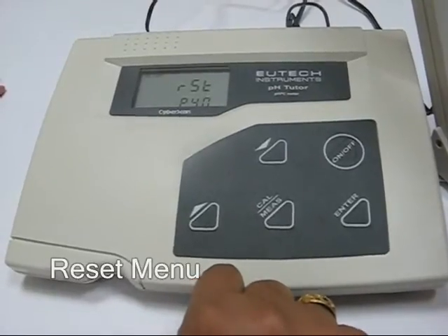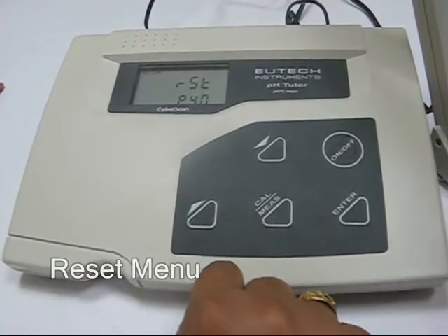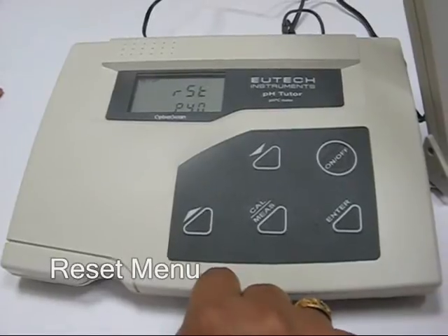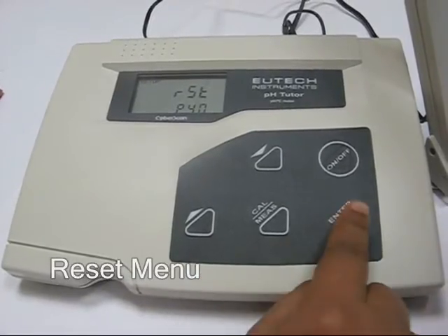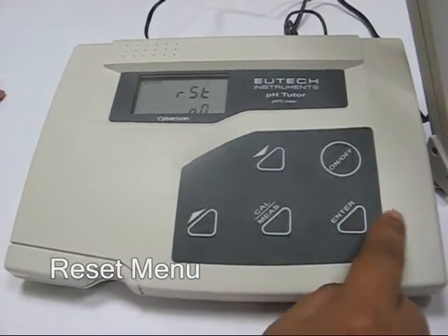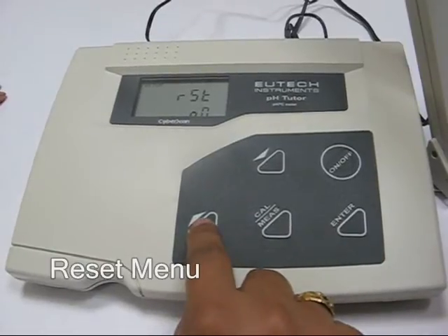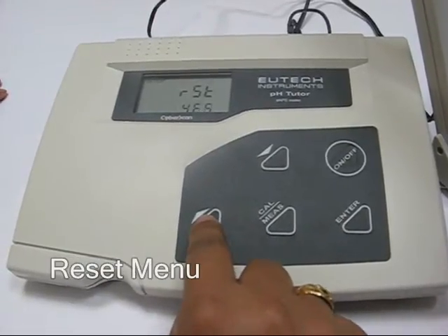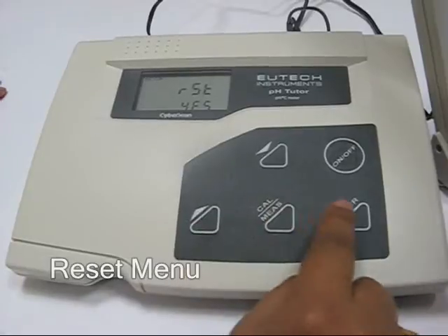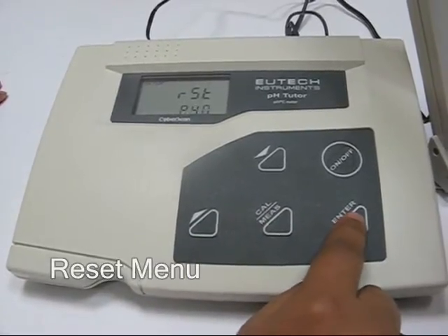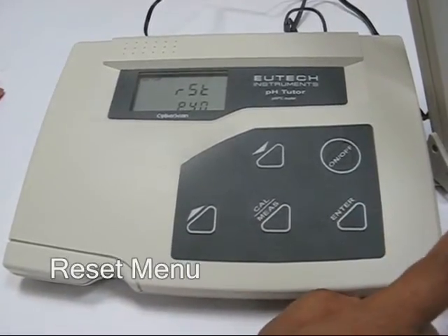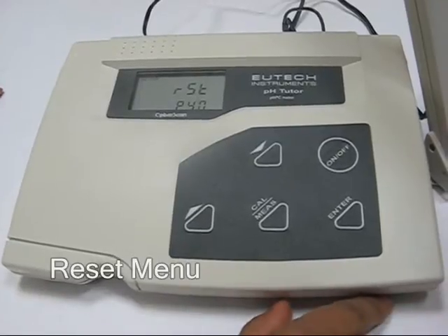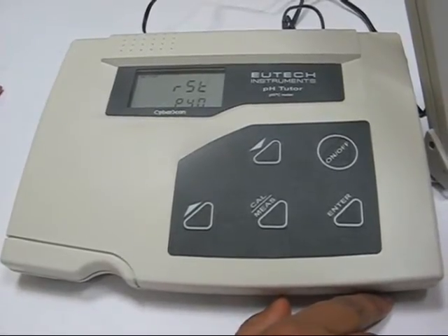If you want to reset the last calibration or the user defined parameters, you come into this menu and press the enter key. Now you will be given two options. The default is no, but you can always select yes. If you press yes and then press the enter key, the instrument resets the last calibration and all the other user parameters that you have selected.